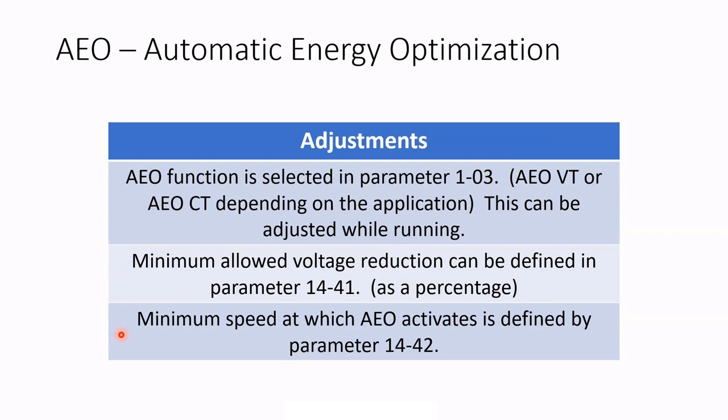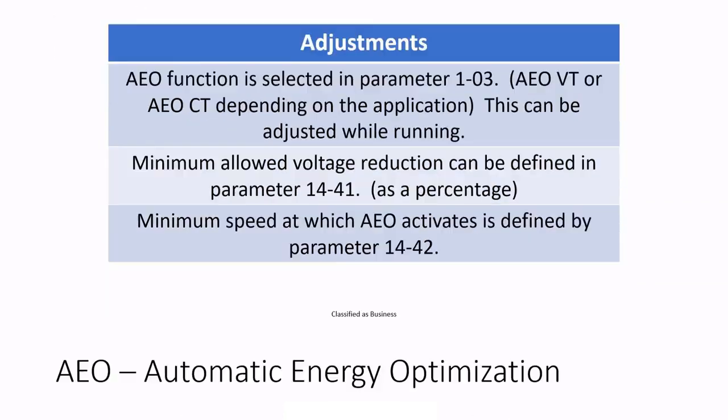Sometimes at very low speeds, the AEO does not act properly. The minimum speed at which AEO activates is defined by parameter 1442, so at lower speeds you can just have the drive run normally.